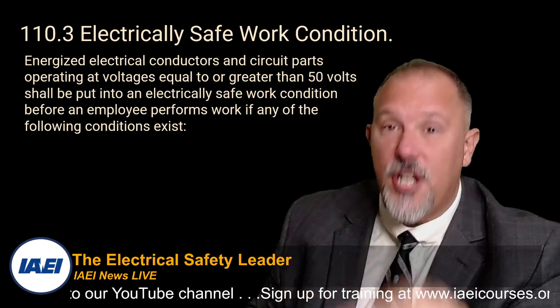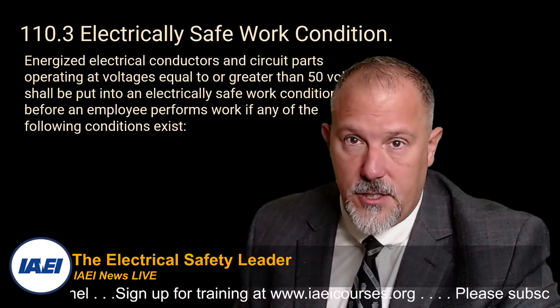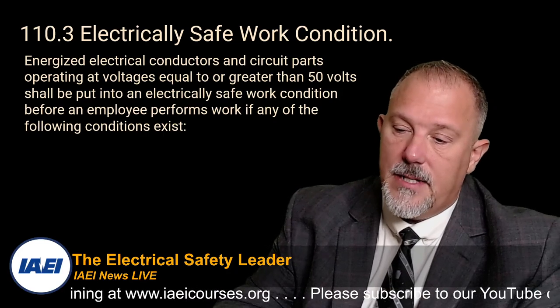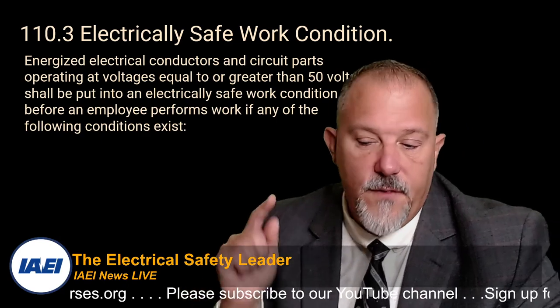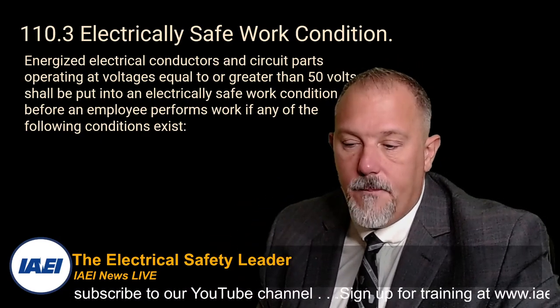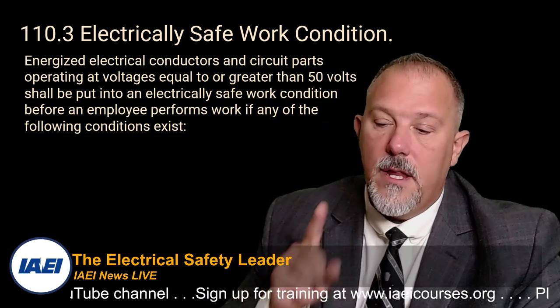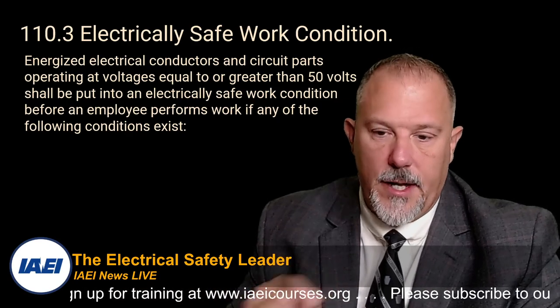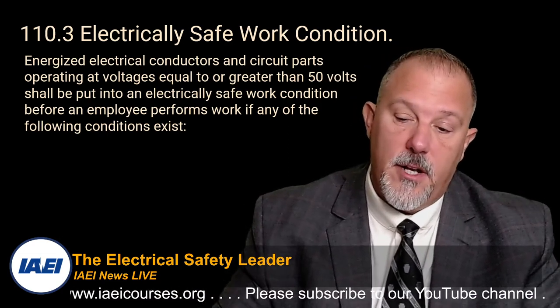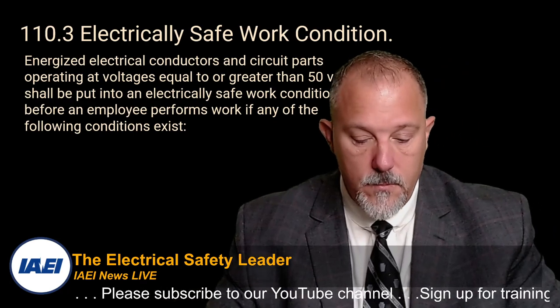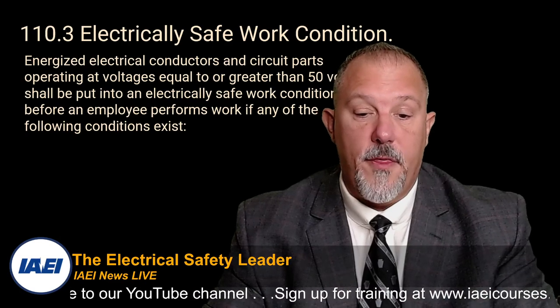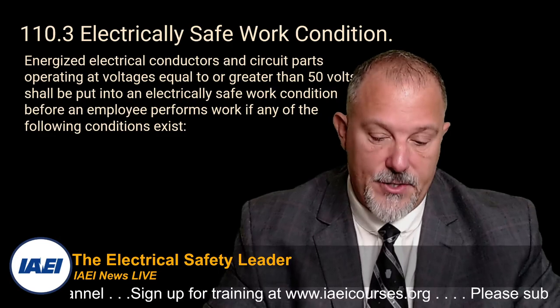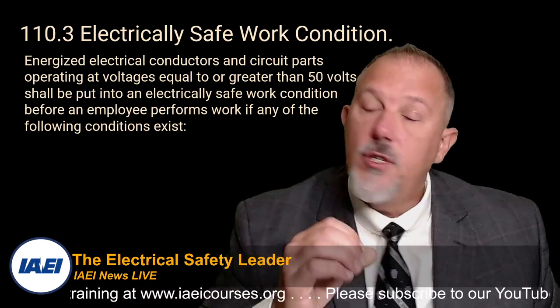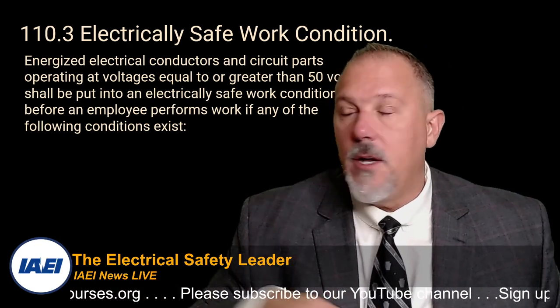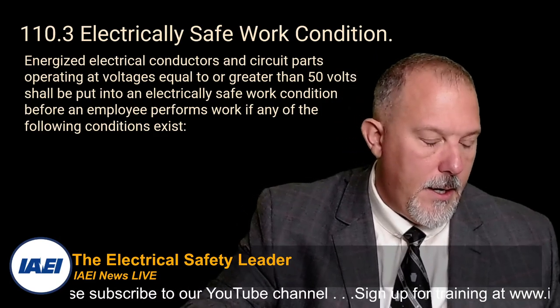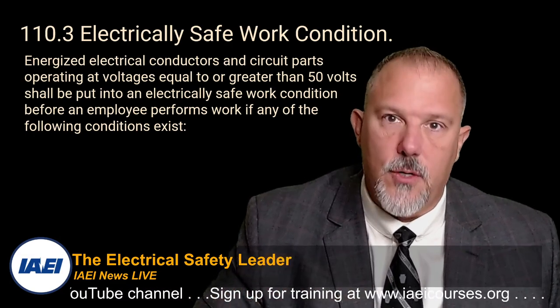So what I know in 110 is that these are general requirements. General requirements apply to all electrical installations. And 110.3 says that energized electrical conductors and circuit parts operating at voltages equal to or greater than 50 volts shall be put into an electrically safe work condition before an employee performs work if any of the following conditions exist. Let's take a look. One, the employee is within the limited approach boundary. Where do we know that? Okay, now we need to understand the limited approach boundary. So where are we going to go there? We're going to go back to the tables, I believe in Article 130, because that's work involving electrical hazards and the limited approach boundary. So remember, the moment you start talking boundaries, you're into Article 130. Why? Because you're talking about working in a state where you have electrical hazards.